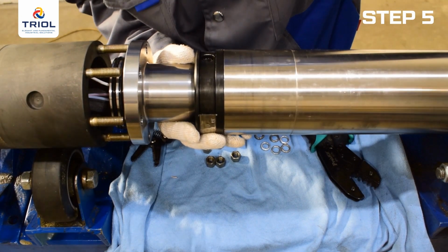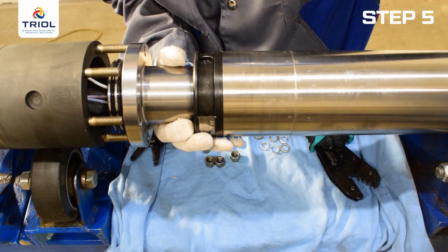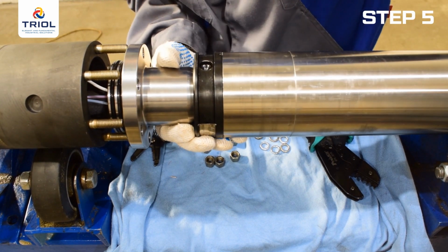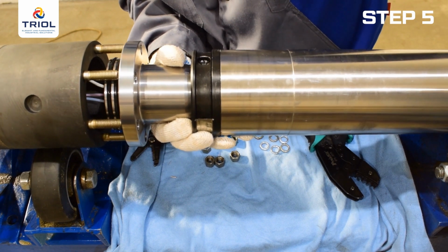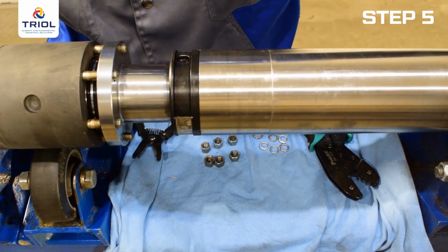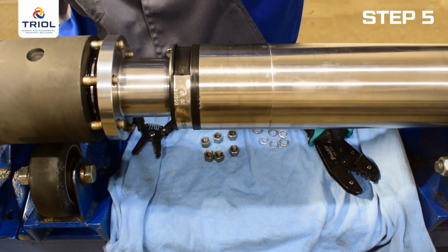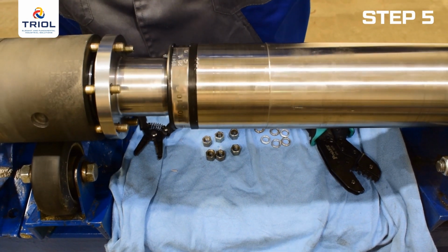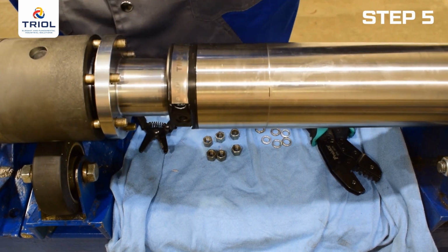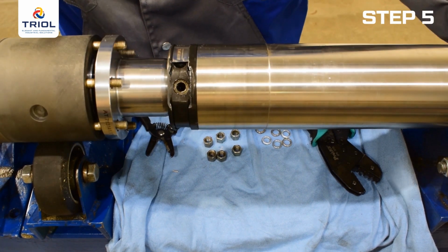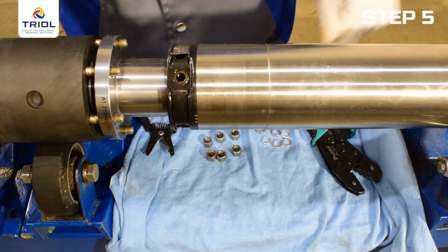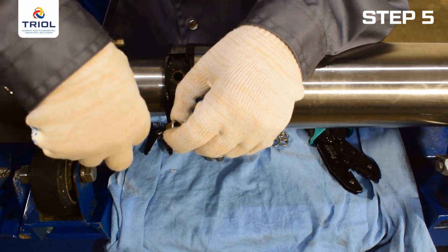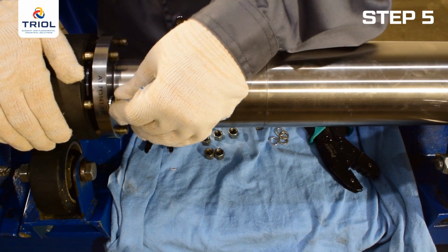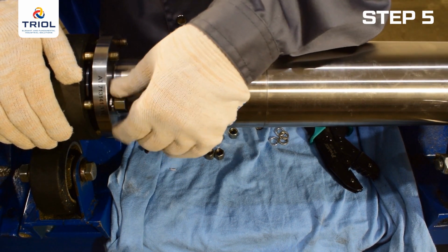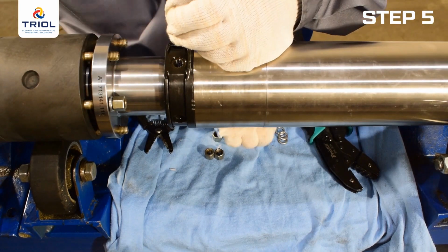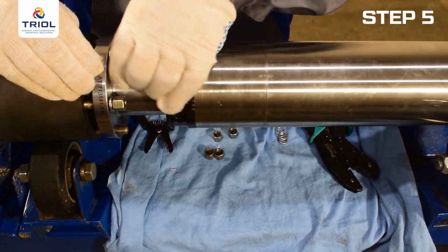Smoothly connect the submersible motor support to the flange of the TM01-10-S, making sure that the wires are not twisted or pinched by the flange. Install the TM01-10-S onto the submersible motor. Check the cleanliness of the mating surfaces, as the tightness of the installation depends on this. Avoid dust, debris, and burrs on the sealing surface. Once the flanges are in contact, screw on and tighten the peripheral nuts with an open-end wrench.